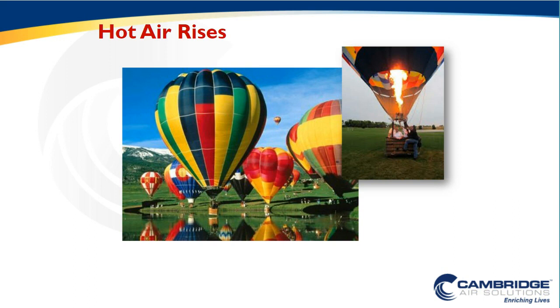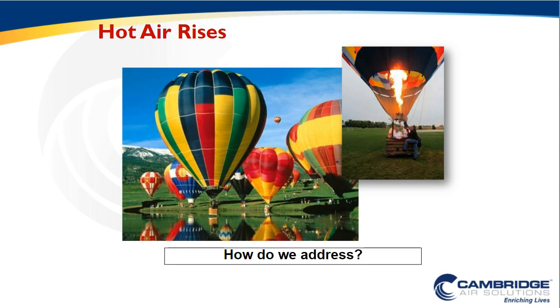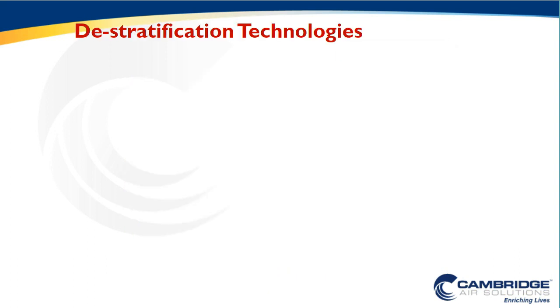When we're trying to heat the floor of the buildings, where our human occupants are, we want to make sure that heat is at the floor and not at the ceiling. And as air and heat want to naturally rise, we must deal with this stratification somehow. So how does HTHV deal with stratification? Well, there are many ways to destratify a space. There are many additional technologies that you can add to a space, whether that's HVLS fans, pair fans, zoo fans, really even simple paddle fans to move the air around and push that warm air that's going to naturally want to rise to the ceiling down to the occupied floor.